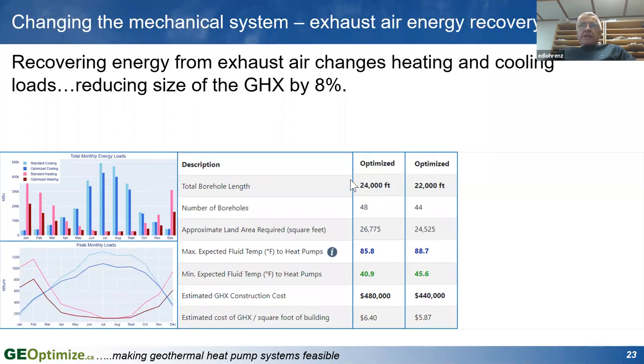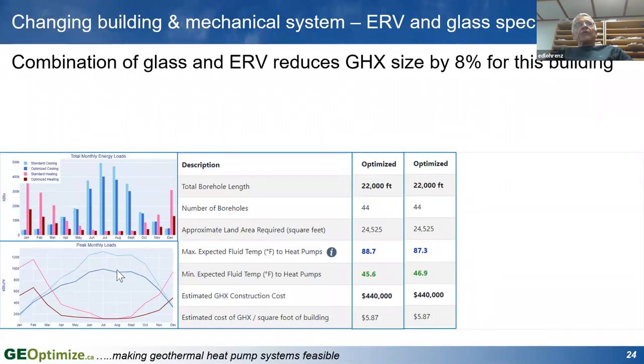Other things that can be done is looking at exhaust air energy recovery. In commercial buildings, in any building, you've got to introduce fresh air to the building to keep it comfortable, and you've got exhaust air. So if you're exhausting 70 degree air to the outdoors and bringing in minus 30 degree air from outside, you've got to heat that air. If you can recover the energy from that air, that changes the cooling loads and the heating loads. And again, that may change the amount of borehole that you need to maintain the temperatures. In this case, it didn't change it much. Here we're looking at both systems, and that's going to vary depending on the type of building, size of the building, and where it's located.